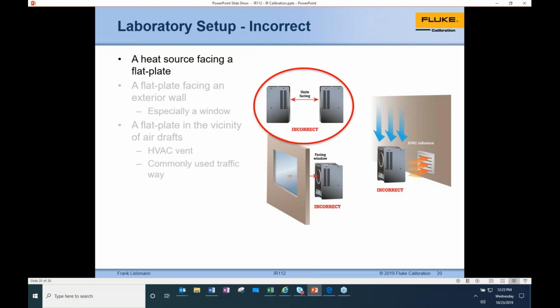Continuing on in the laboratory setup, these are just some real basic tips on setting up units. You don't want to have units facing each other, because basically you're going to be passing radiated energy back and forth. We didn't really jump into emissivity, but it's kind of a percentage, so think of it as 0% to 100%. Most things we're talking about or working with are spec'd at what we call 0.95, or 95%, meaning it's emitting 95% of its energy. A perfect black body is described as 1, so you get 100% of that emitted energy back out of it. So units facing each other could be like putting a hairdryer on an ice plate - you're going to have them fighting each other.